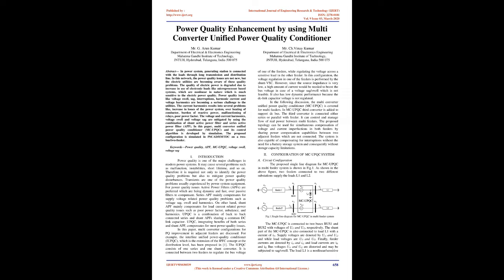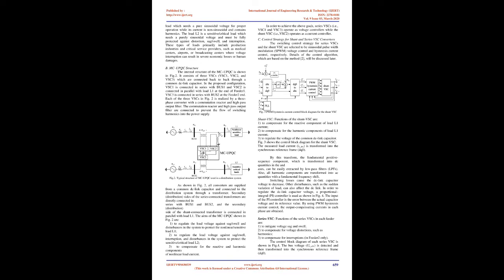In this configuration, the voltage regulation in one of the feeders is performed by the shunt VSC. However, since the source impedance is very low, a high amount of current would be needed to boost the bus voltage in case of a voltage sag/swell, which is not feasible. It also has low dynamic performance because the DC link capacitor voltage is not regulated. In the following discussion, the Multi-Converter Unified Power Quality Conditioner, MCUPQC, is covered for multi-feeders.